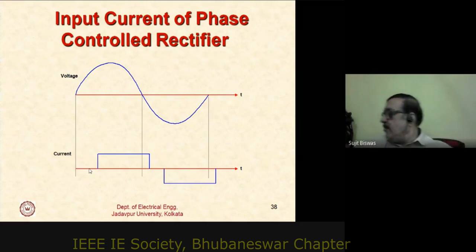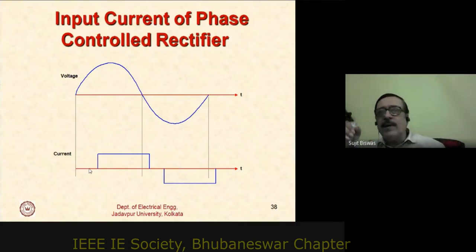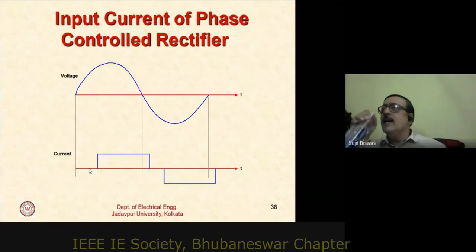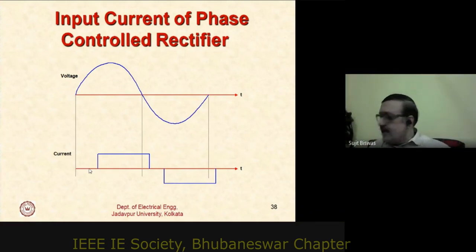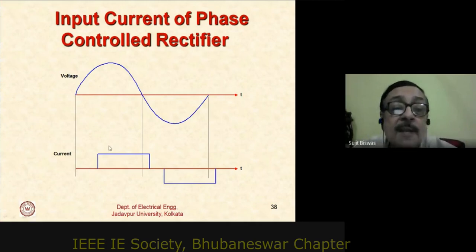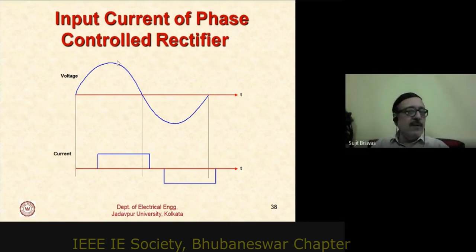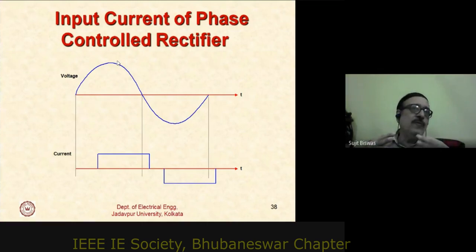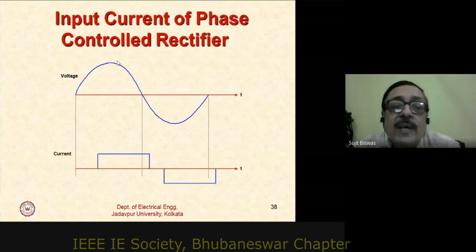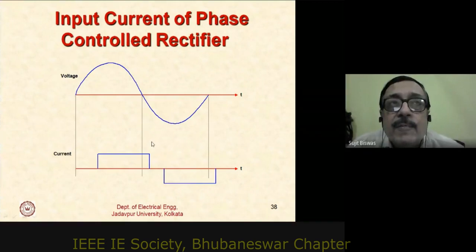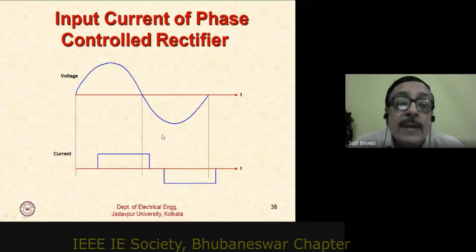The worst case is a three-phase phase-controlled rectifier, where the current waveform is ideally a rectangular 120-degree conduction waveform shifted from the voltage zero crossing by the phase shift angle. This gives approximately 33% total harmonic distortion plus a poor displacement factor — a double degradation of power factor. That is why the use of phase-controlled rectifiers is declining, though at large power ratings they remain the industry workhorse due to reliability, simplicity of design, and the rarity of thyristor failures.